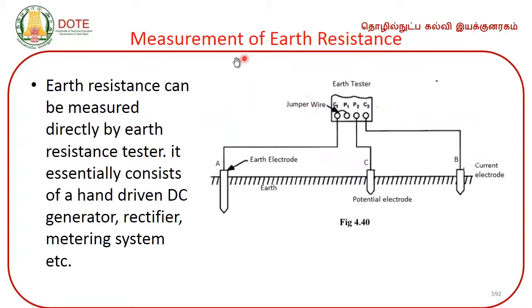Then we will move on to the very important topic of measurement of earth resistance. So, here is the arrangement for the measurement of earth resistance, which is called an earth tester. There are 3 electrodes available here: the earth electrode, the potential electrode, and the current electrode, which is represented as B. The potential electrode is represented as C, and the earth electrode is represented as A.